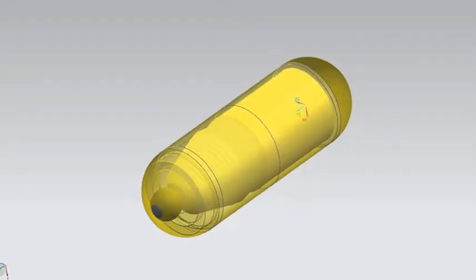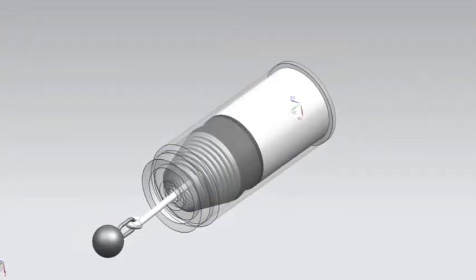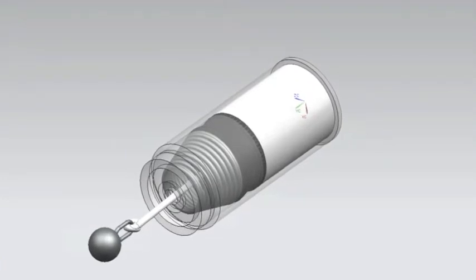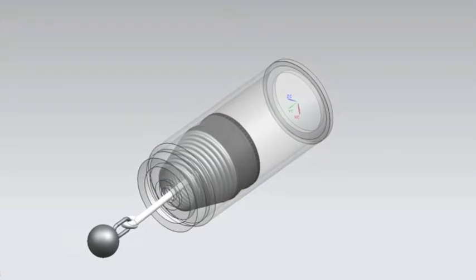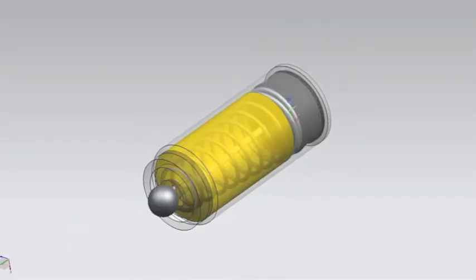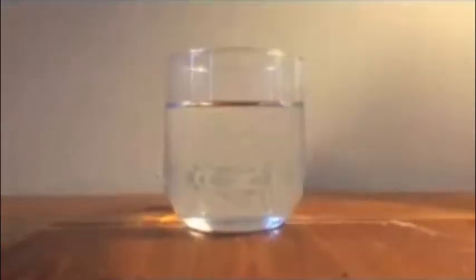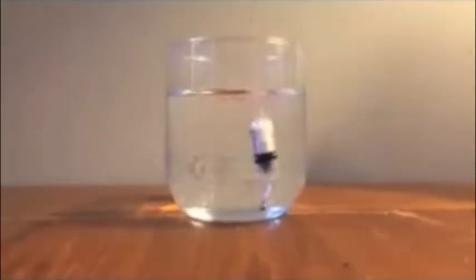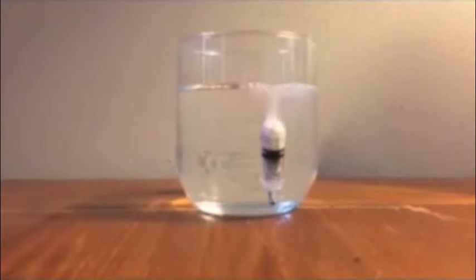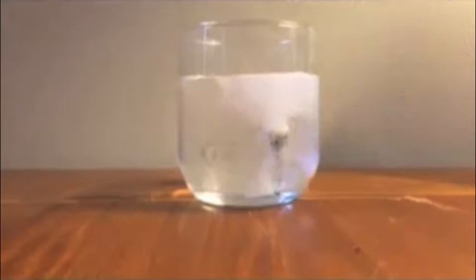The difference is in our approach. We aim to work with rather than against the body by condensing the gastric lavage process into a self-sealing smart pill that collects bacterial sample in the stomach. The device is placed in the upper esophagus using a specially designed delivery tool. A lubricant coating facilitates passage of the device into the stomach, where the acidic environment dissolves the basic contents of the device, allowing the internal sponge to expand and suction tuberculosis-laden gastric acid into the internal compartment. A tethered plug then seals off the collected sample, preventing bacteria loss and enzyme entry in the intestinal tract.